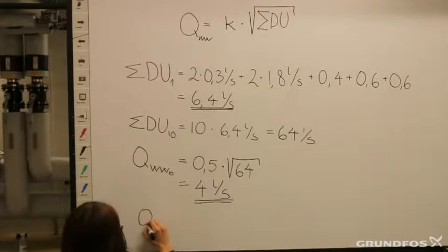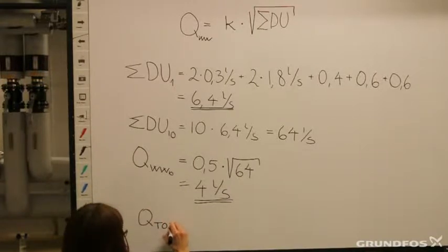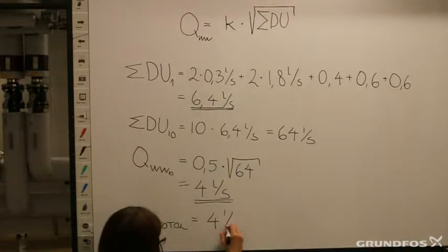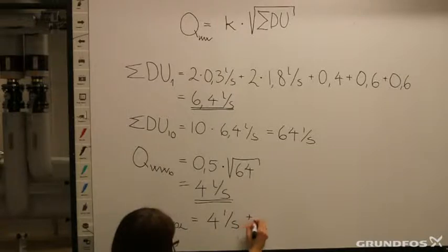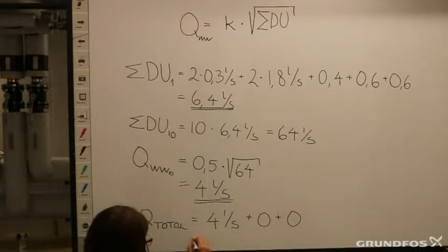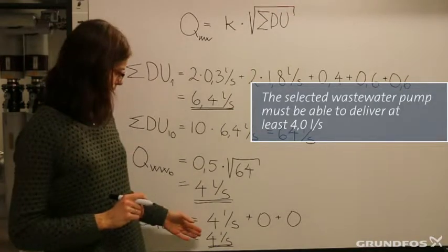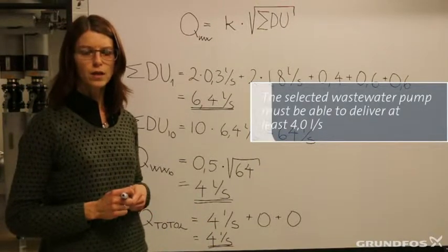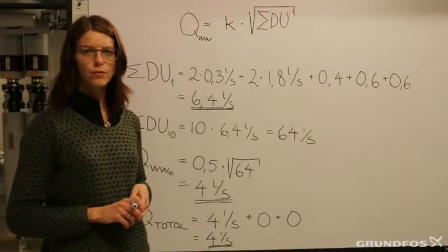Q_total will then be 4 liters per second for the wastewater, plus 0 for the continuous flow rate, plus 0 for the pumping flow rate. So we have a total flow rate of 4 liters per second. This means that we must select a pump which can move at least 4 liters per second to have an efficient wastewater system to discharge the wastewater from this building.